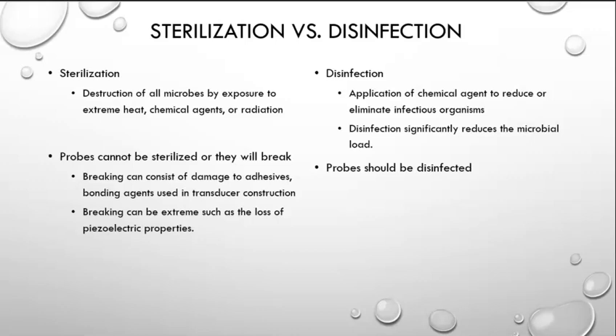So what exactly is sterilization? Sterilization is the destruction of all microbes by exposure to extreme heat, chemical agents, or radiation. Okay. Disinfection, on the other hand, is the application of chemical agents to reduce or eliminate organisms. Disinfection will significantly reduce the microbial load on an item, whereas sterilization will remove the microbial load, including the bacterial spores. Probes cannot be sterilized or they will break. Okay, if you try to sterilize a probe, you will destroy it.